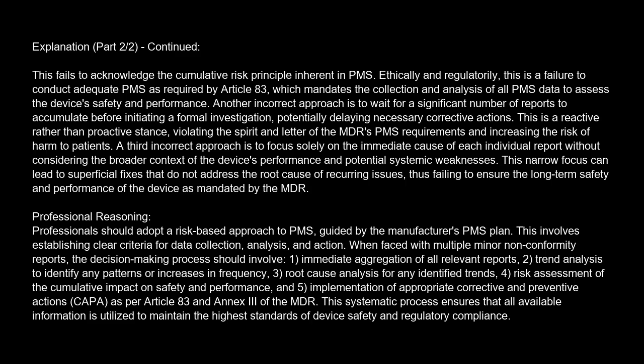Another incorrect approach is to wait for a significant number of reports to accumulate before initiating a formal investigation, potentially delaying necessary corrective actions. This is a reactive rather than proactive stance, violating the spirit and letter of the MDR's PMS requirements and increasing the risk of harm to patients.